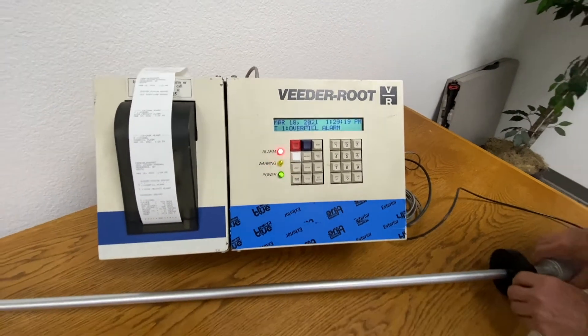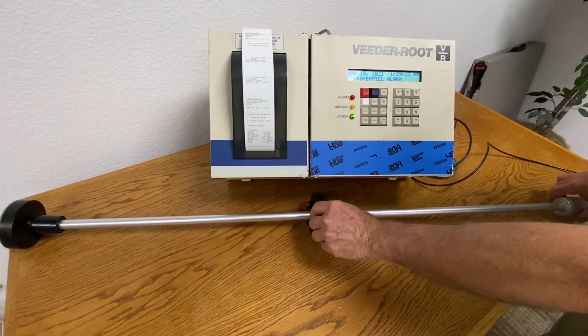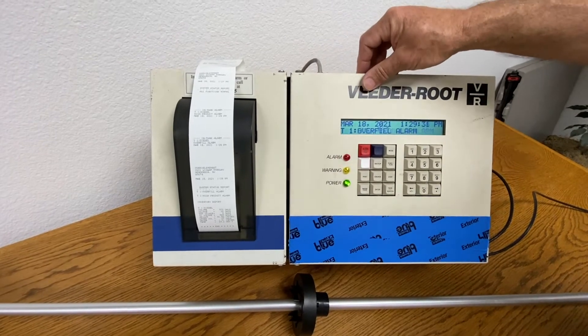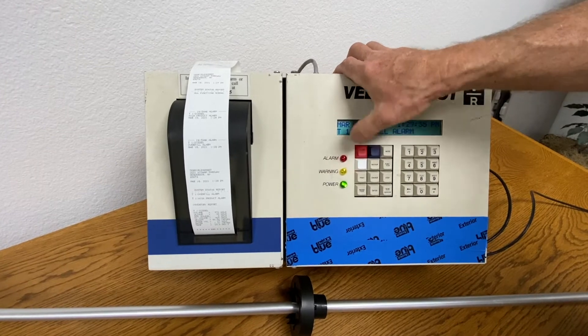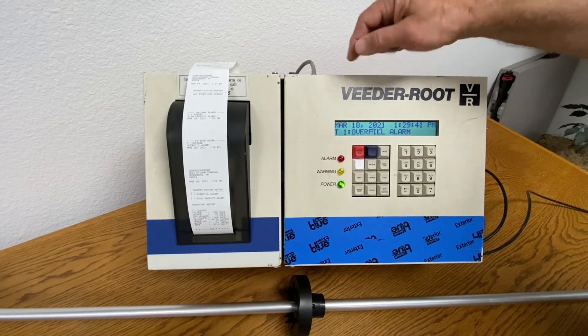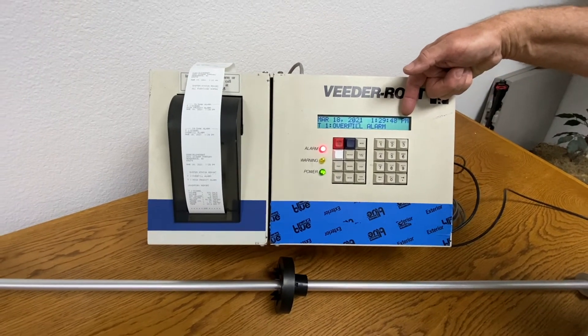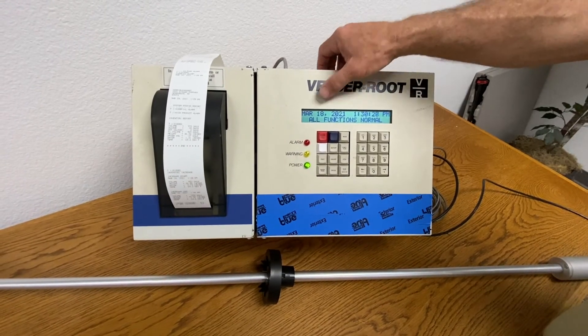As the fuel is being sold out of the tank, the probe float will go down to its normal operating condition, and within one minute your high level alarms and warning light alarms will go out. By pressing the red alarm condition button you acknowledge that the alarm was cleared. Sometimes it takes up to one minute for the overfill alarm light to clear, and then it will clear and the light will go out. There it is — all functions normal now.